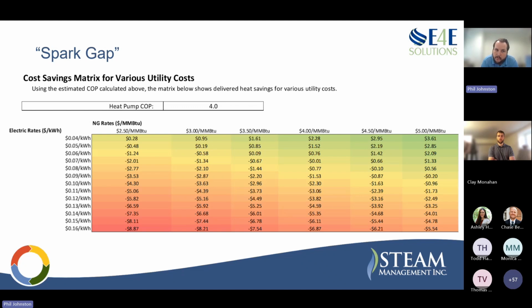This will all change depending on the performance too. So that COP is really going to drive that electric performance, and if you can get that COP at a higher value, it's going to drive the financials of this as well, which lines up with what Clay said earlier. So this slide right here really shows how these two variables drive the financials of a project. If you have high gas and low electricity, it's going to look much better. And if that performance on the heat pump, the COP, is really high, that's also going to be very helpful for the project.